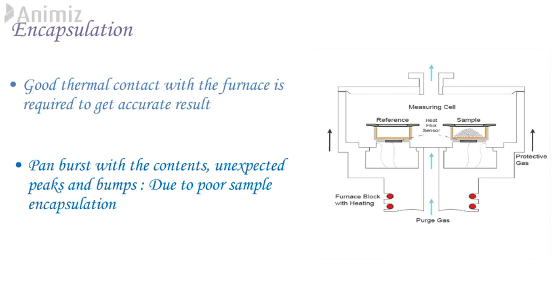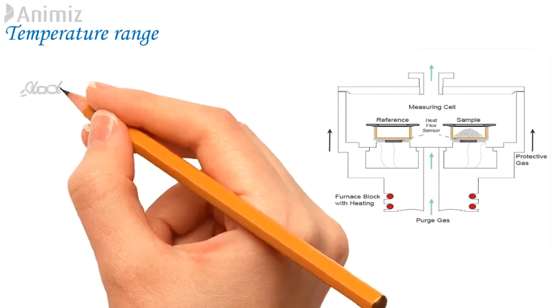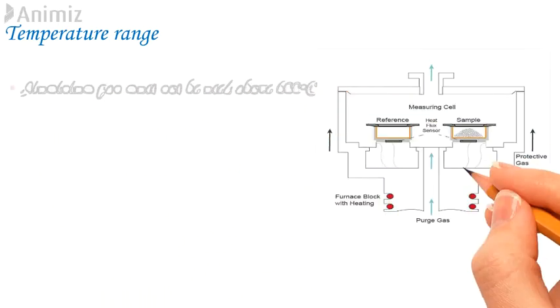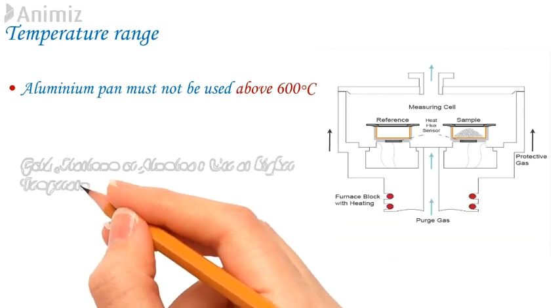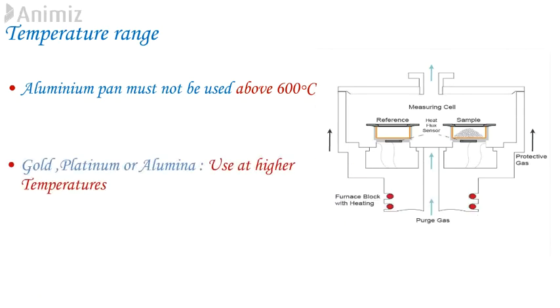Most manufacturers provide a range of sample pans for different purposes with a range of different sizes, pan materials and associated temperature and pressure ranges. 2. Temperature range. Make sure that pan is specified for desired temperature range and will not melt during scan. Remember that aluminum must not be used above 600 degrees Celsius. Pan material such as gold, platinum or alumina can be used at higher temperatures.